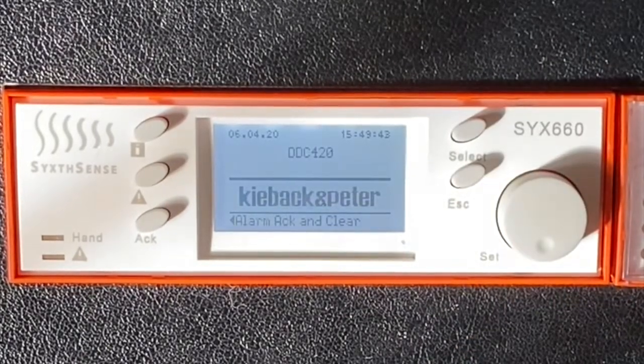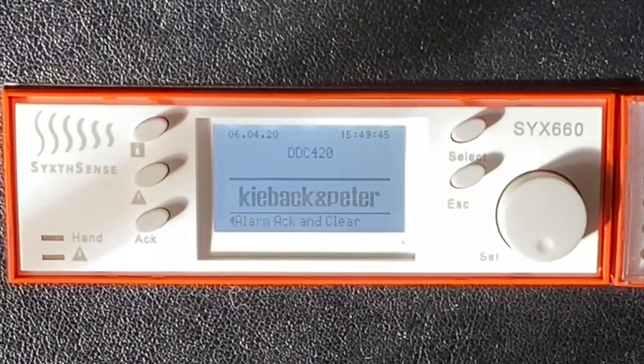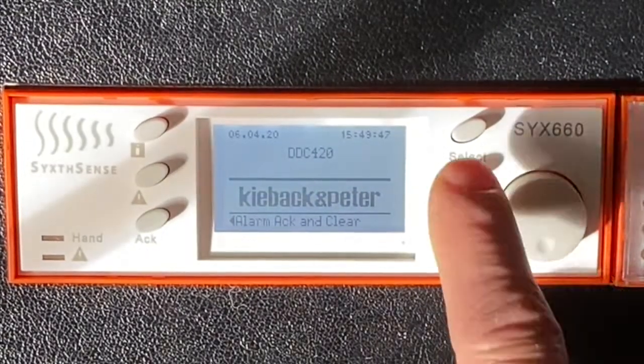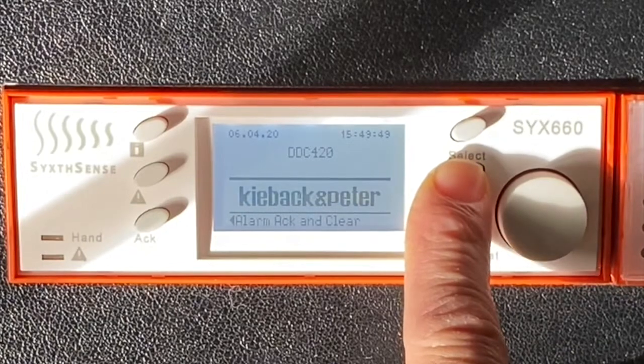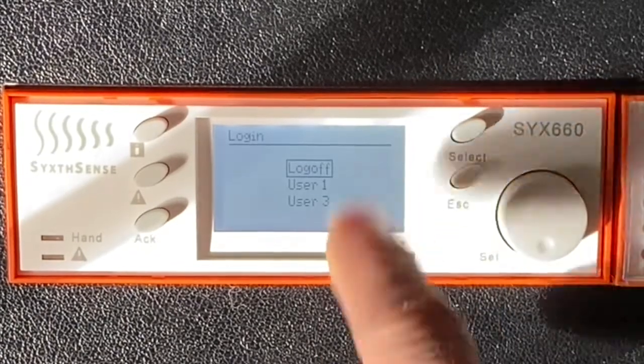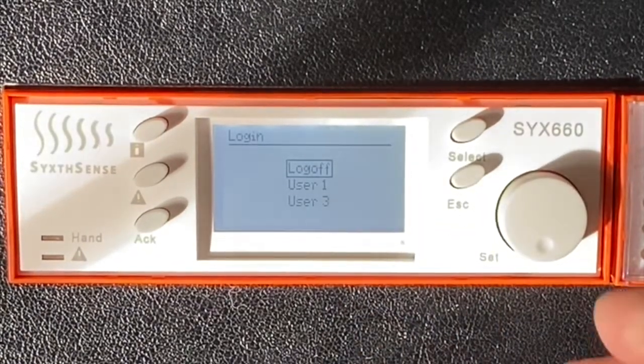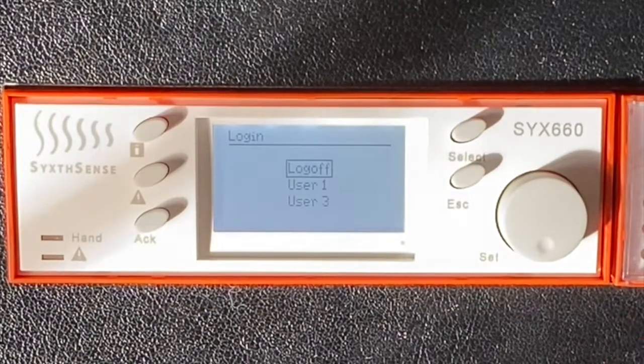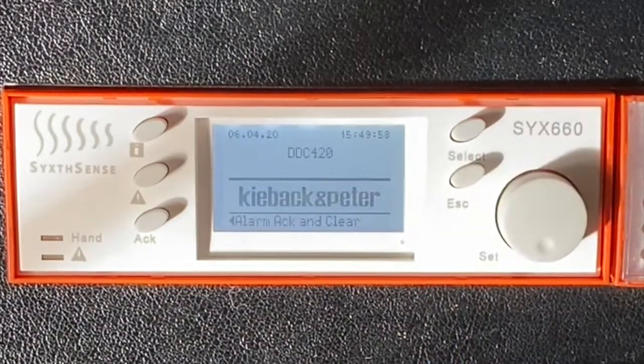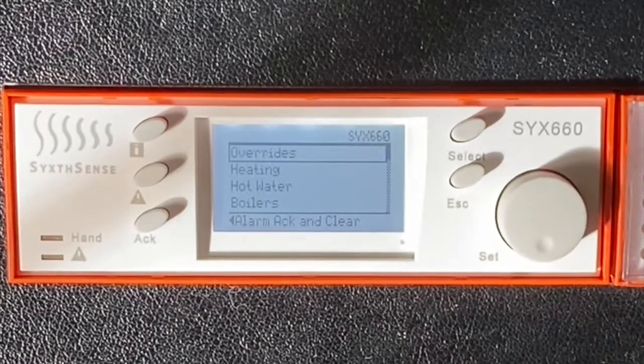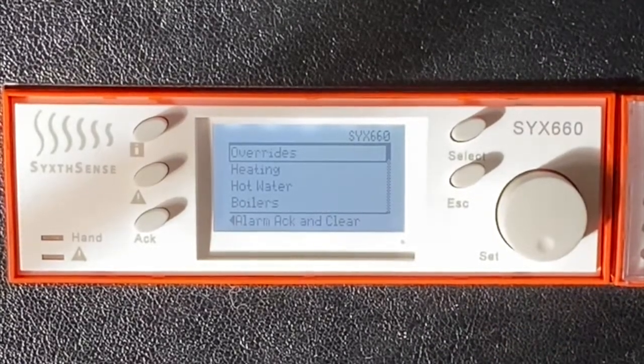Okay, so now we're logged in at user level 2. You can check the user level you're logged in at by holding in the escape key once more. You can see that user 2 is no longer available and we get the option to log off. We don't need to do that, we're just going to press escape. Now we access the main setup or the main operating menu.